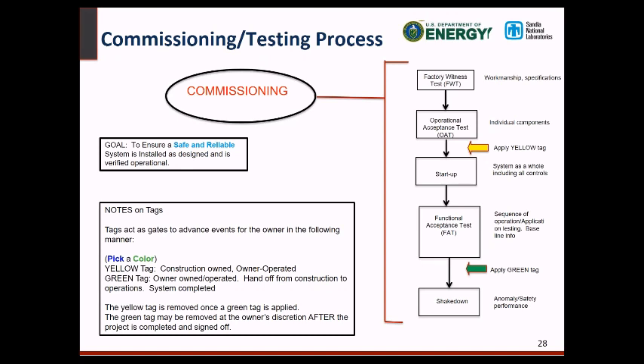This is the part where it turns over to your operation and maintenance group that will start to do the startup, and this is what we call a yellow tag, which is applied. At this point, the people that are doing the commissioning now own the equipment. They will do the startup, and they're going to do a functional acceptance test, which is the application of the energy storage. Once the system has been deemed that it can function and is doing what it needs to do, it is then turned over to the owner. Once the owner has it, if the operation and maintenance people want to work on it, they have to go through the owner. So at this point, the owner is the one that owns the system. And then we go to a shakedown, which typically happens semi-annually or annually. It's like turning off the actual power from the utility to the energy storage system, making sure it shuts down safely, and then when you restore power, that the system comes back in a safe mode.